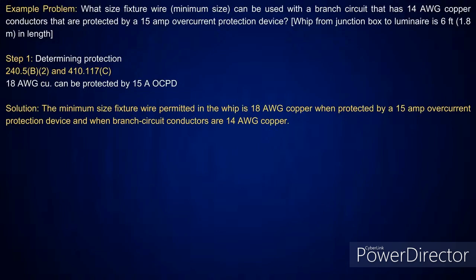Sure, I understand the terminology. When you look at this, you've got 240.5(B)(2) to determine the protection, and it's not in 240.21, because they're telling you here that number 18 can be protected by a 15 amp overcurrent device.